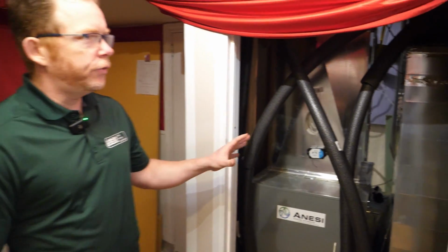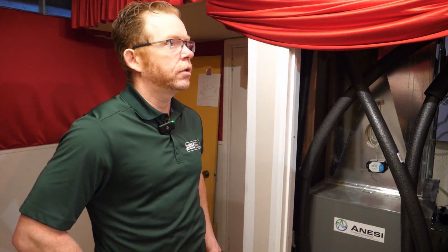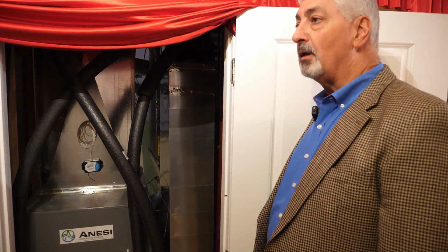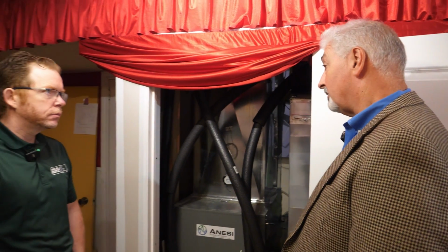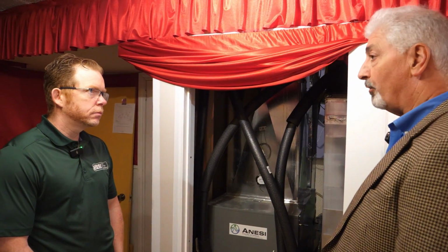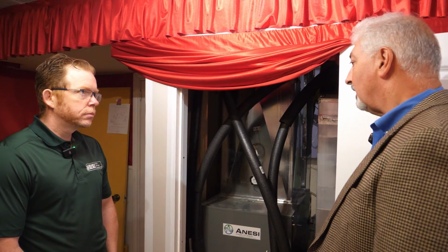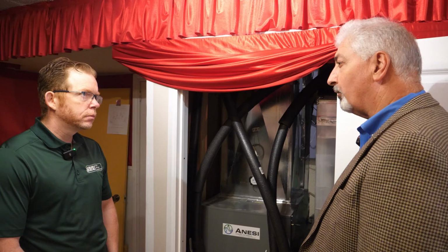Yeah. What kind of a delta T does this piece of equipment work on going out to the outdoor unit into the indoor unit? It needs a 20-degree delta T to really optimally operate at peak efficiency. Okay, and what would the range be? So if 20 degrees is your max efficiency, what would be your minimum, what would be your maximum this equipment could run at? Our maximum that we can supply to is about 150. We prefer to operate in the 140 range. Sure. So coming back, I think our minimum coming back is in the 112 range.